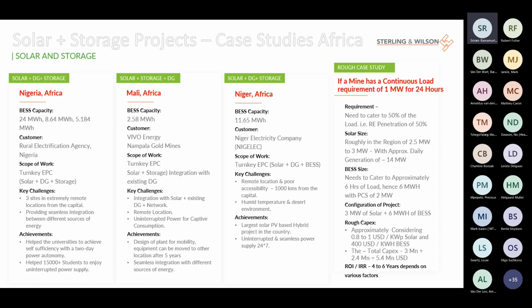With 2.5 to 3 megawatt of solar, we'll generate approximately 14 megawatt hour of load. Not all 14 can go to the grid at the same time since it's a 1 megawatt load; at some point solar will generate 1.5 to 3 megawatt, depending on size, irradiation, and other factors.